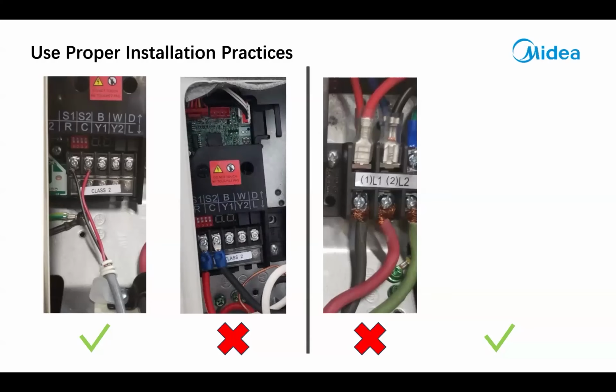All right, so on your communication cable, I don't like to see crimp-on terminals on the communication cable because they create a choke point for the communication. Also on communication, while we're on communication, no wire splices in my communication cable. If you're going to have to splice the wire on the communication cable, I will only accept a soldered connection.